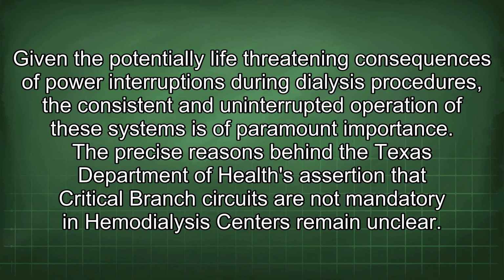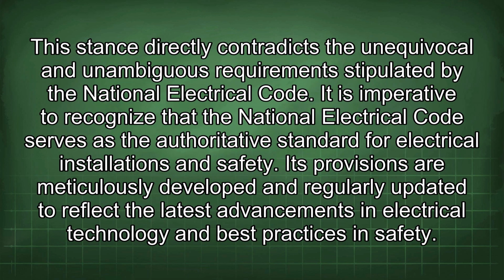The precise reasons behind the Texas Department of Health's assertion that critical branch circuits are not mandatory in hemodialysis centers remain unclear. This stance directly contradicts the unequivocal and unambiguous requirement stipulated by the National Electrical Code. It is imperative to recognize that the National Electrical Code serves as the authoritative standard for electrical installations and safety.